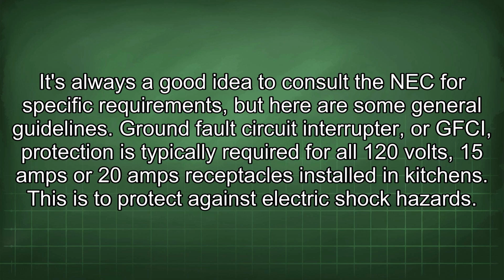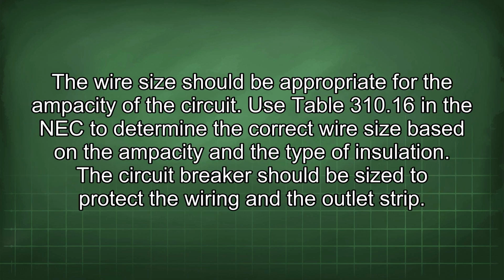Ground fault circuit interrupter, or GFCI, protection is typically required for all 120 volts, 15 amps or 20 amps receptacles installed in kitchens. This is to protect against electric shock hazards. The wire size should be appropriate for the ampacity of the circuit. Use table 310.16 in the NEC to determine the correct wire size based on the ampacity and the type of insulation. The circuit breaker should be sized to protect the wiring and the outlet strip.